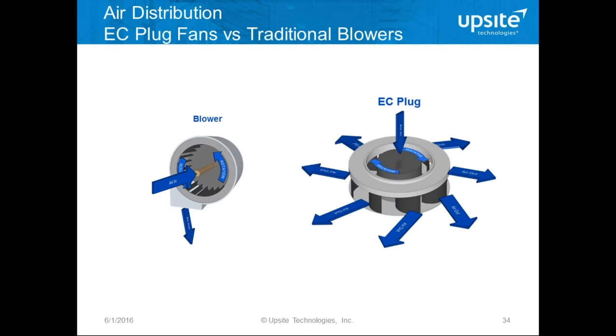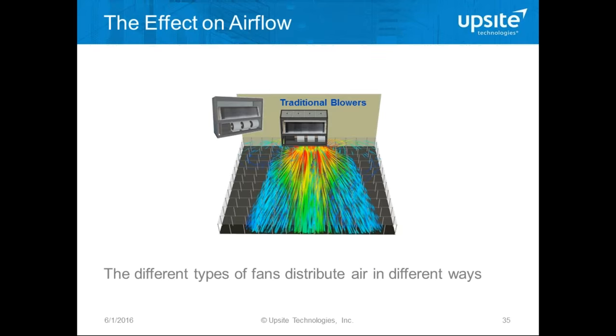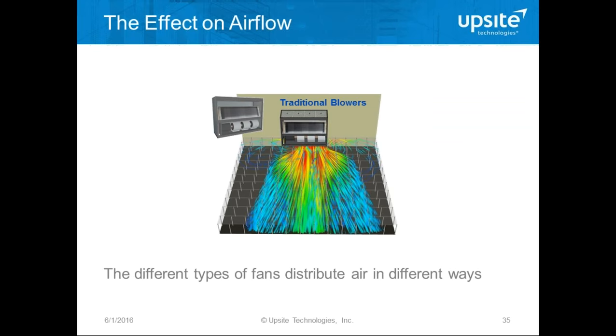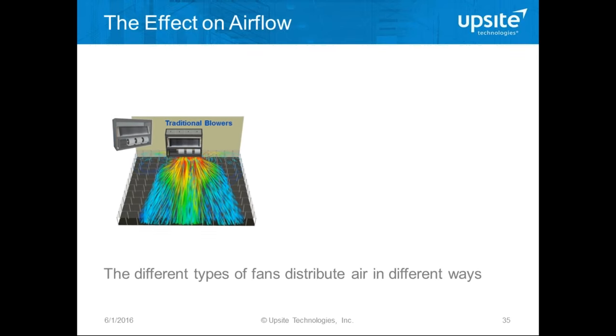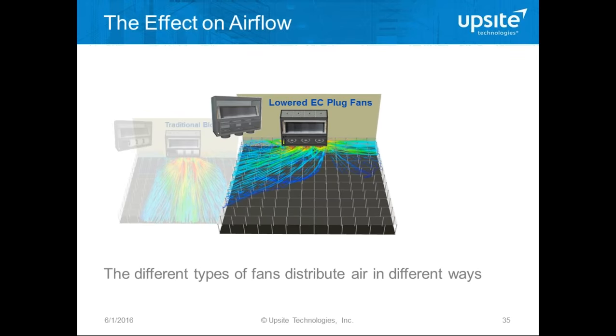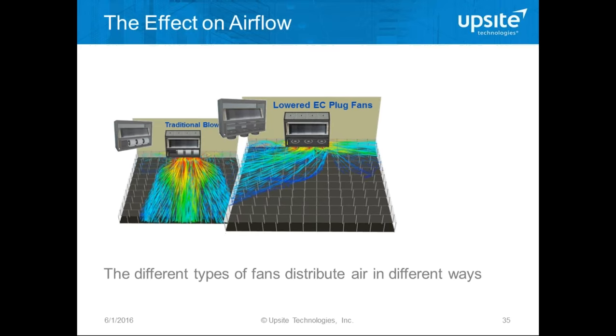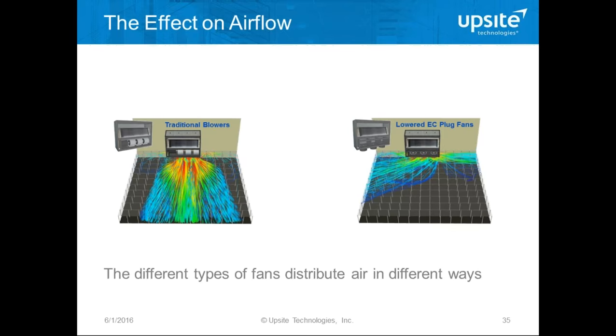EC fans are fundamentally different to traditional centrifugal blowers in cooling units — the flow pattern is quite different. Traditional blowers create air that comes down out of the cooling unit, hits the solid floor, and tends to be distributed forwards and to the sides. EC fans create a plug flow and are often installed dropping down into the raised floor. The rotational motion results in airflow going in a very different pattern, which may or may not be a problem in the room.